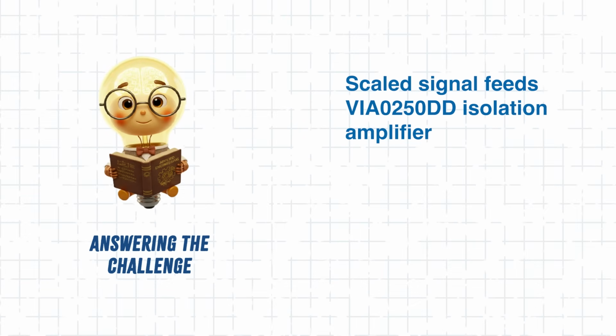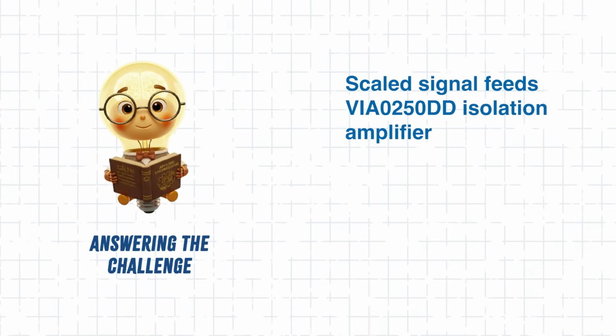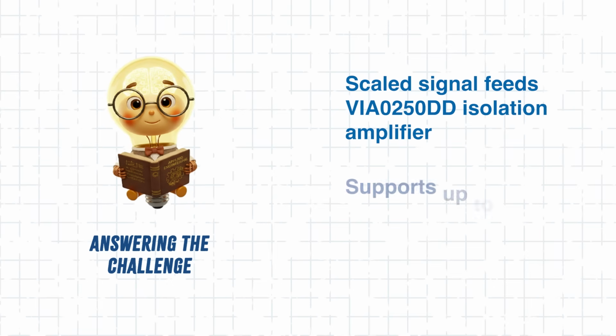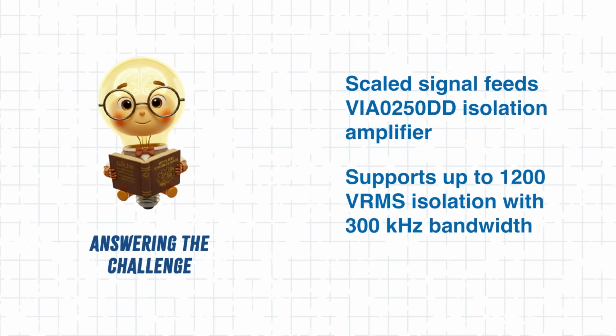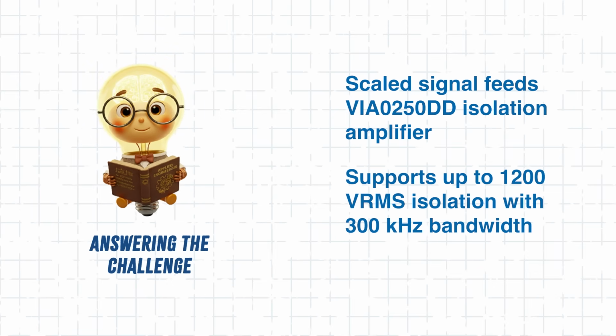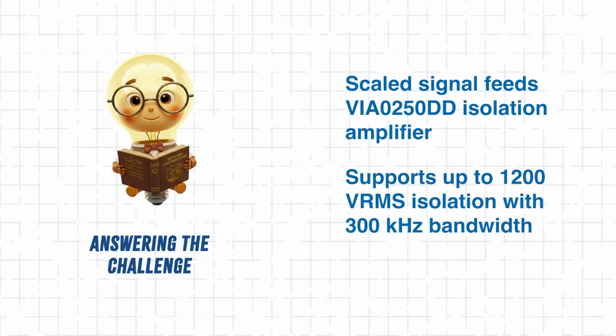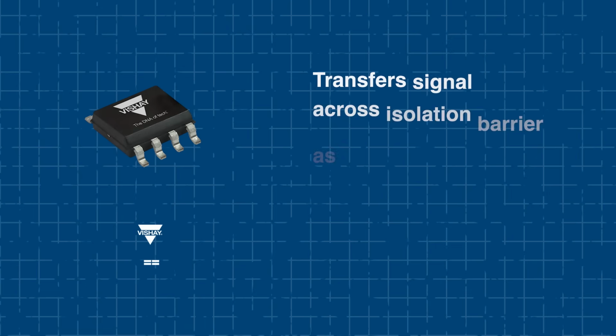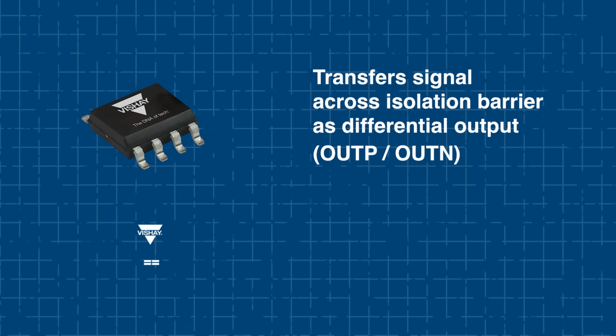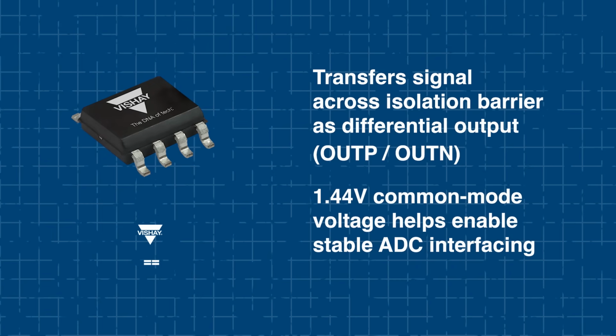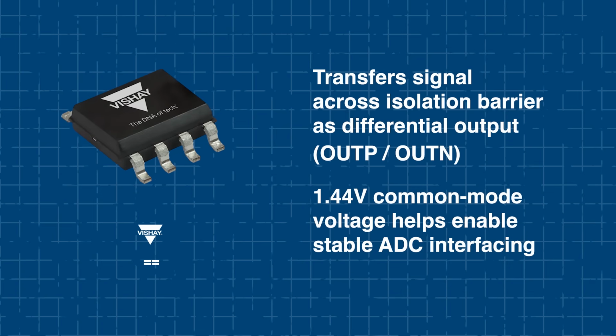The scaled signal feeds into the VIA0250DD isolation amplifier, which provides up to 1200 VRMS working isolation while maintaining a wide 300 kHz bandwidth for dynamic AC measurements. This amplifier reproduces the input signal across an isolation barrier and outputs a differential analog signal at out P and out N. The defined 1.44 volt common mode voltage helps ensure predictable downstream interfacing while maintaining reinforced electrical separation between high voltage and low voltage domains.